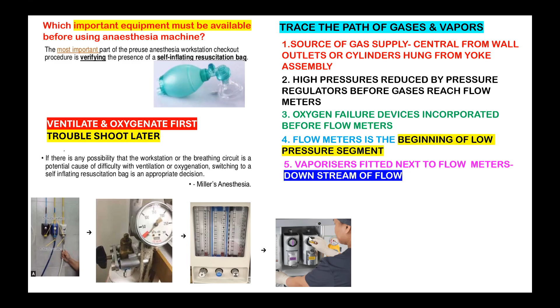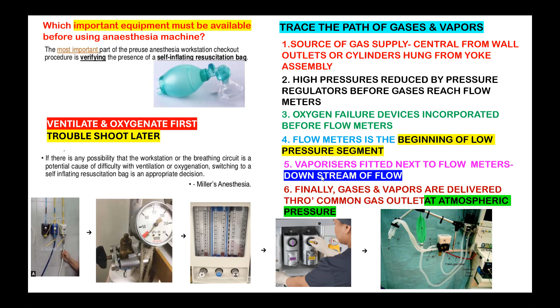Okay. So these are all the steps from the source, pipeline or cylinder, reduced by the pressure gauge, come to the flow meter. If you want to use a volatile, you pass the flow meter gas into the vaporizer, and then deliver it to the patient through the breathing circuit. So these are the 6 steps. Source of gas, high pressure reduced by the pressure gauge, oxygen failure safety measure, then the gases flow through the flow meter, flow through the vaporizer, finally comes out through the common gas outlet at atmospheric pressure. Okay, so this is how the whole gas travels and reaches the patient.